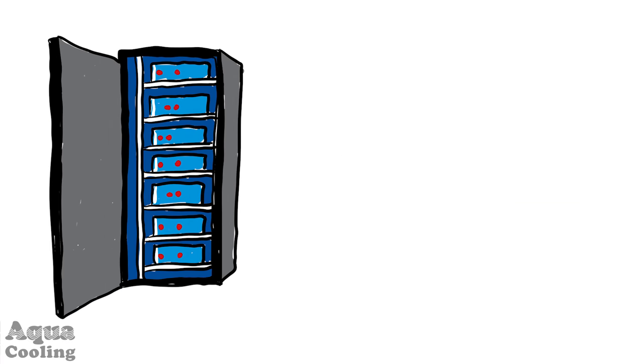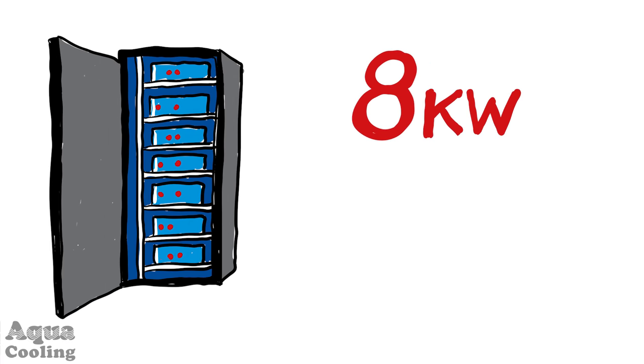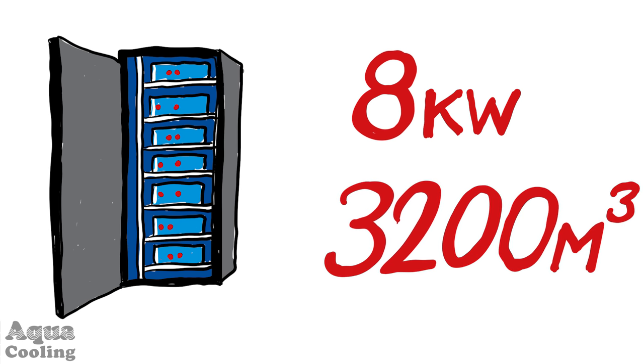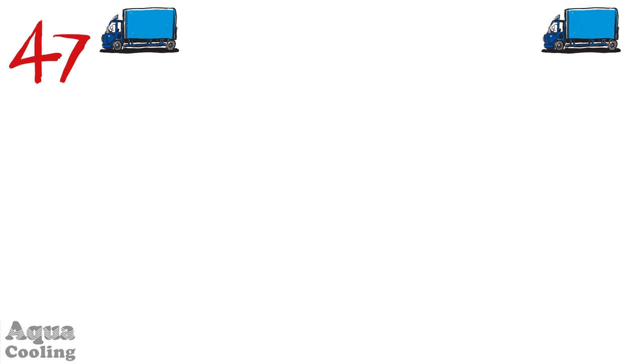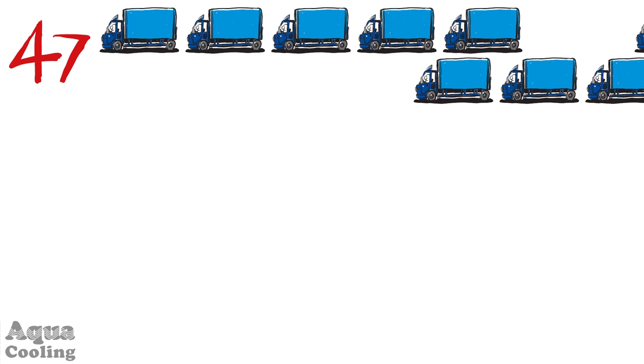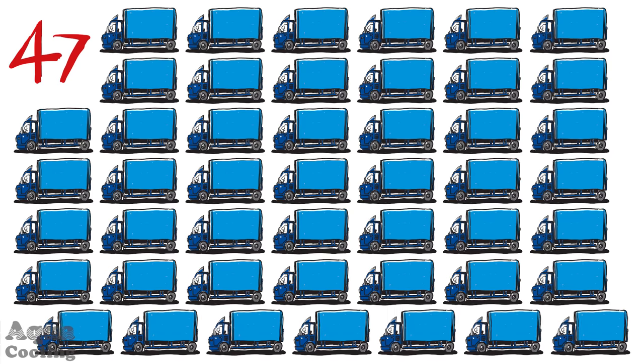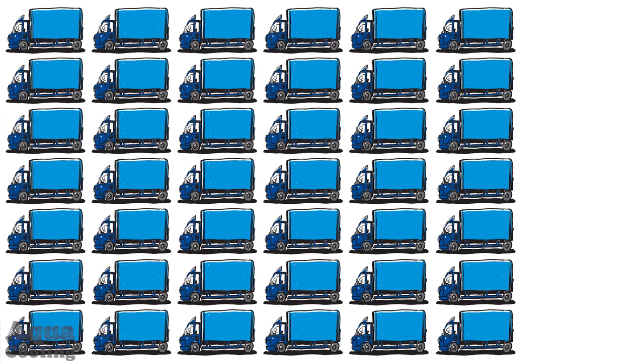Just look at the numbers. To cool an 8kW rack takes an astonishing 3200 cubic meters of airflow per hour. That's the equivalent of 47 40-foot trucks delivering air every single hour for just one 8kW rack.